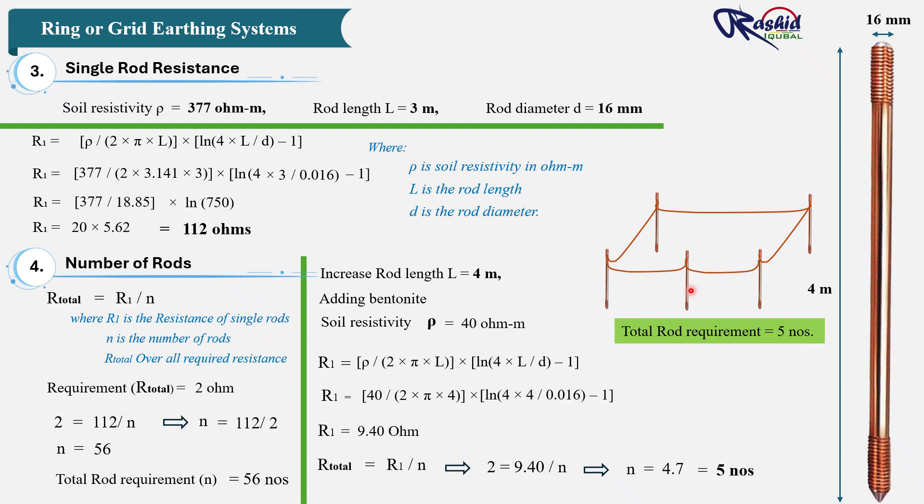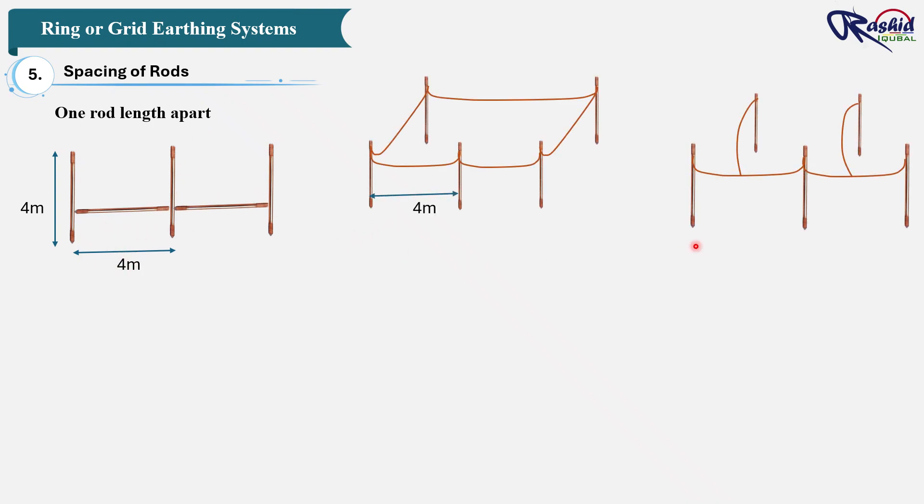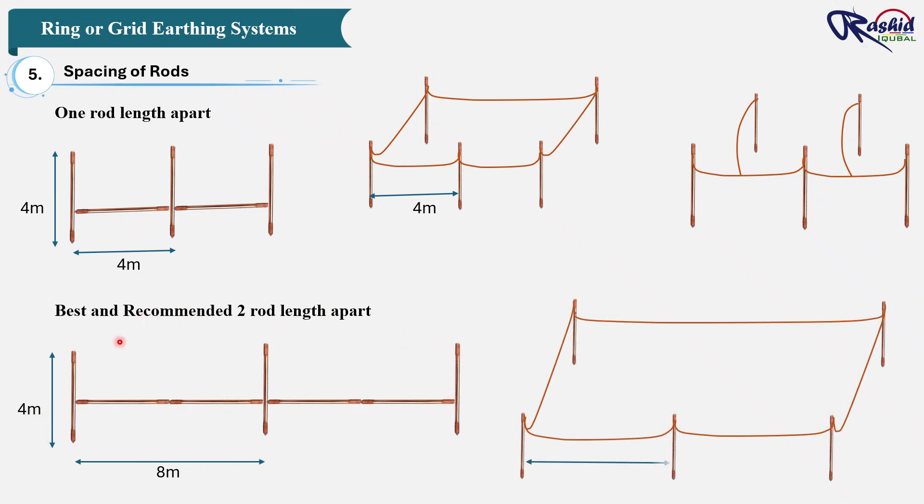Once we find out the number of rods, then the question arises here: what distance should be maintained between rods? That's why we will learn here spacing of rods. To minimize mutual resistance, rods should be spaced at least one rod length apart. And if space allows, there is sufficient space, then twice the rod length is even better. This proper spacing ensures that each rod works effectively without overlapping electrical fields, giving us better overall performance of the earthing system. For 4 meter rods, use spacing of 4 to 8 meters between rods around the building perimeter.